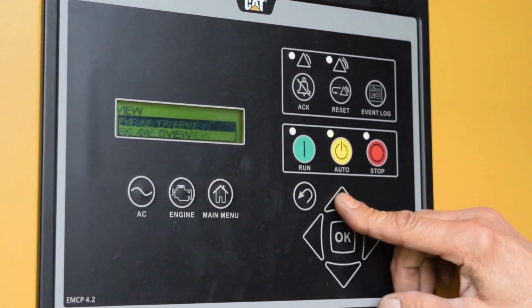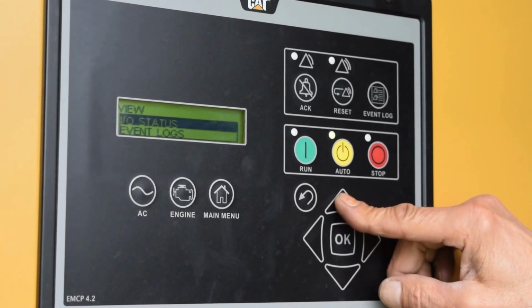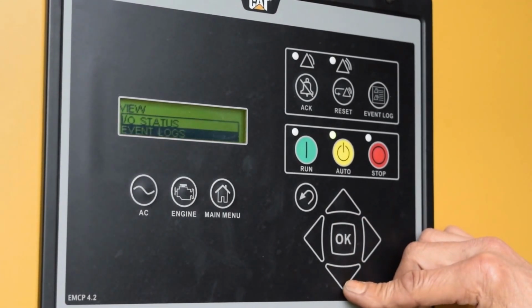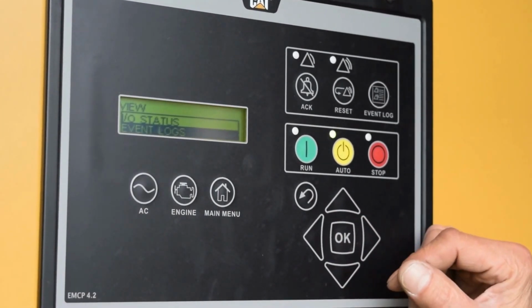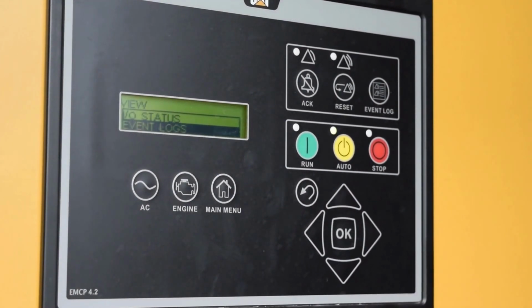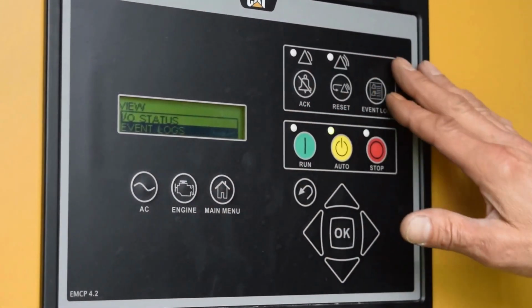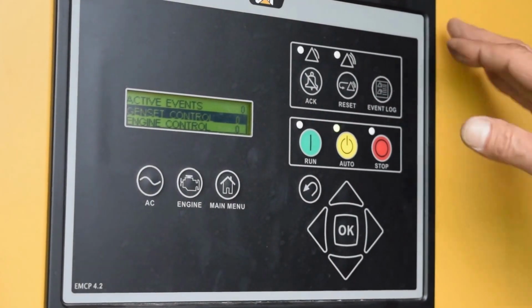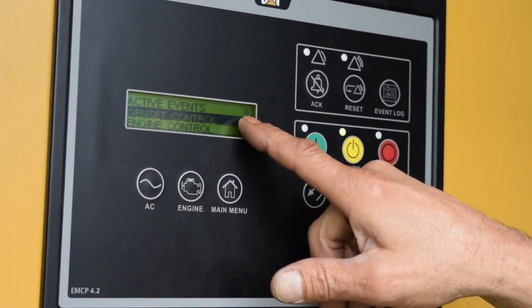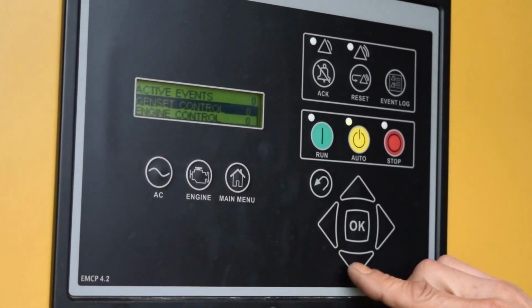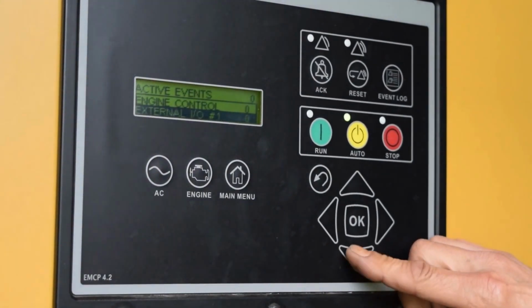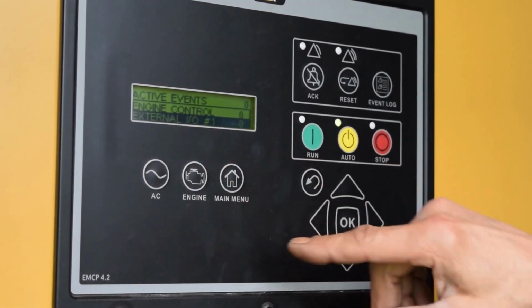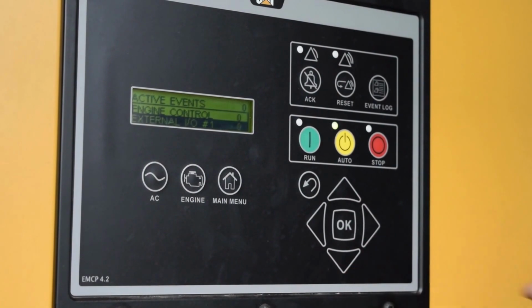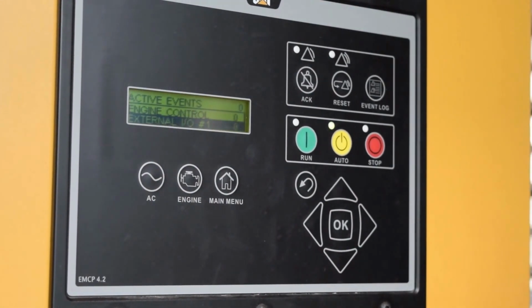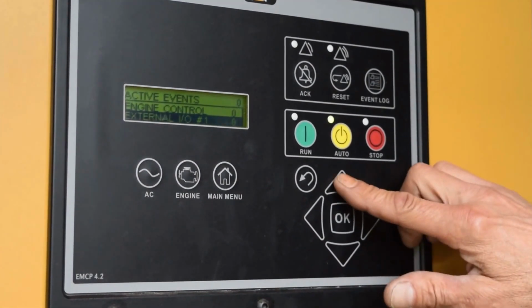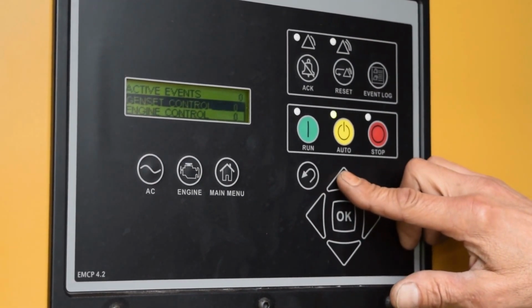Some of the earlier ones that we talked about, first the IO status and event logs, those are good for diagnostics. IOs are more so for a technician, but your event logs, and you don't even have to go, your event log is right here. As you can see, active events, there are none. There are none in the genset controller, there are none in the engine controller. There's an external input-output module, there are none in there. There are faults, however, logged in there that were events that happened prior.